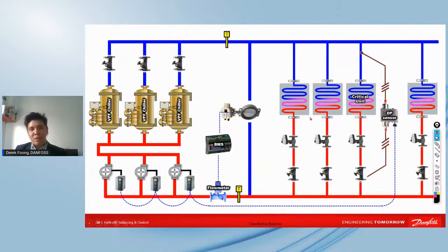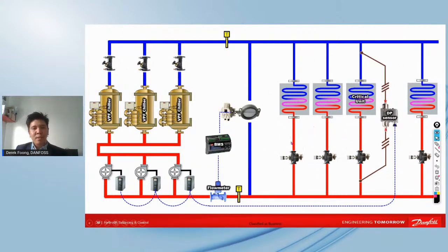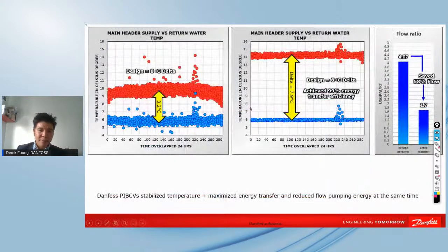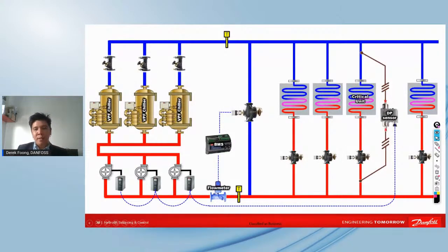And once we replace the inferior valves in the system, what is also important right here is the bypass. Most of the time you can see there's a butterfly valve here, and to compound the problems, they put an on-off butterfly valve, which is very heartbreaking at those times. And of course, this can also be changed to pressure-independent technology. It's also very important at this part. And sorry, I will roll back a little bit before we come to the analytics. Now, when we look at systems, we very often look at the kilowatt per ton, and in a very crucial energy.